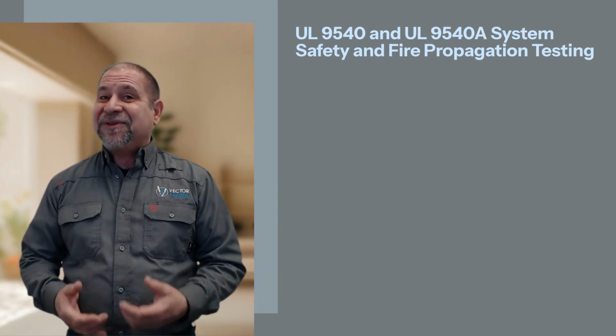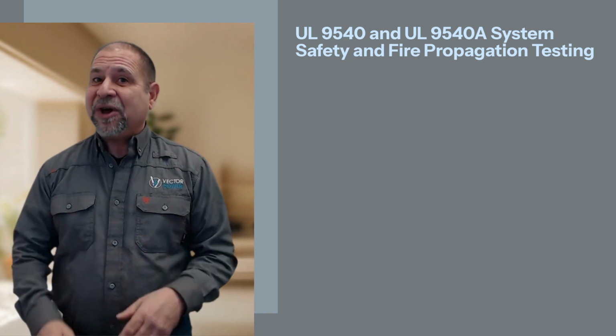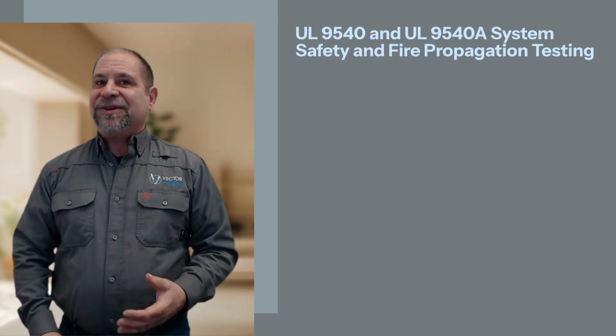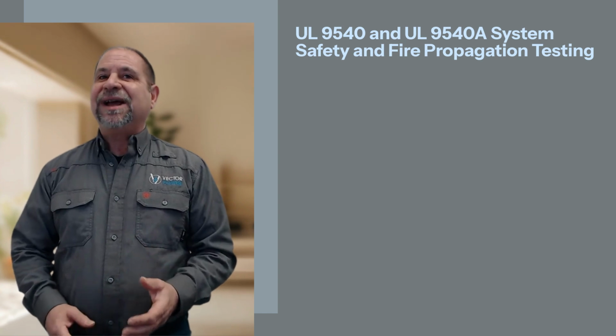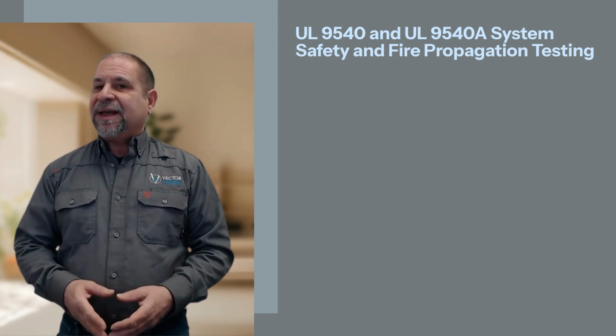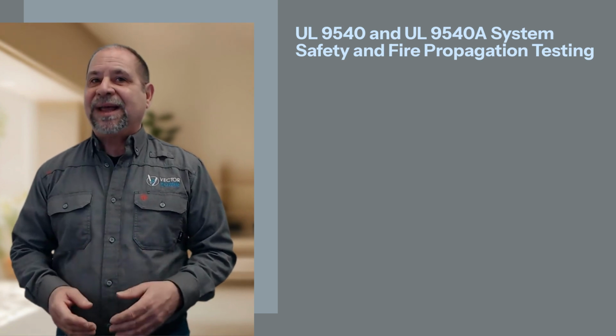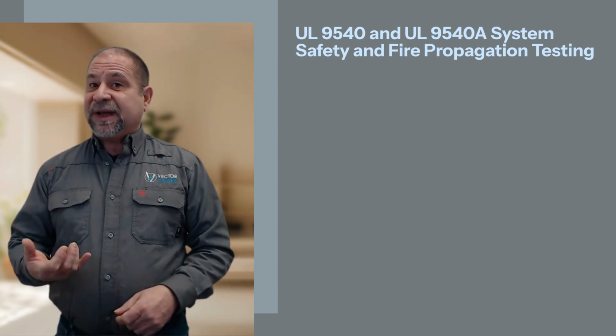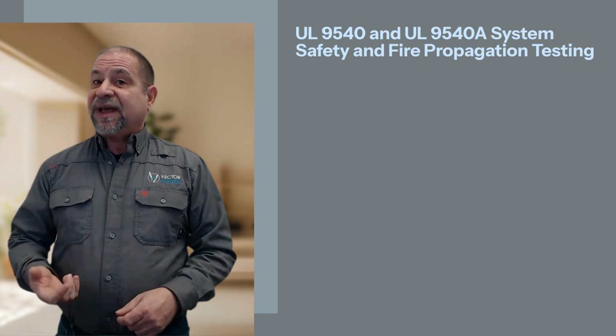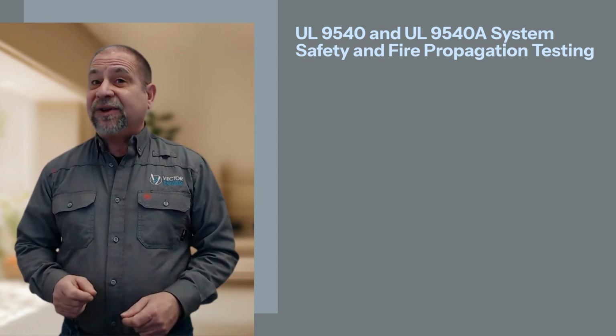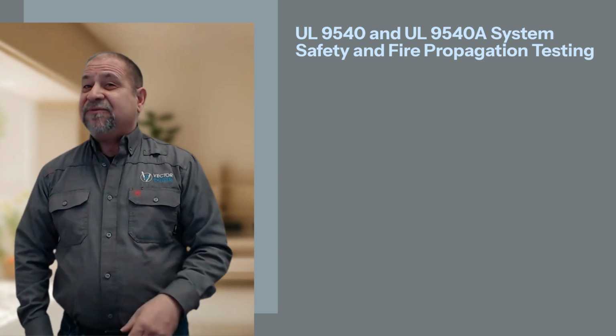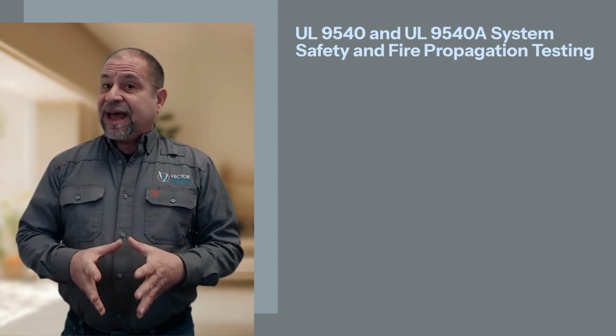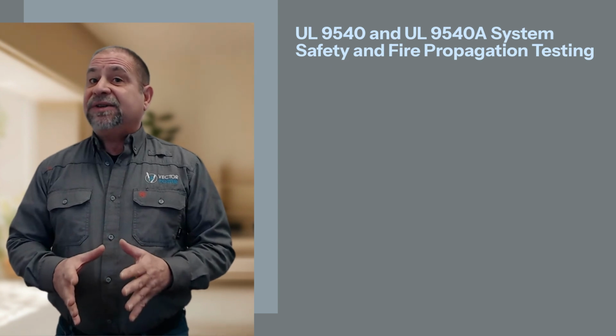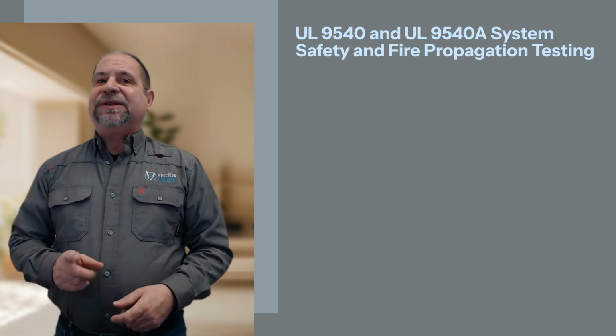NFPA 855 and related fire codes explicitly reference UL 9540 and UL 9540A. In many jurisdictions, energy storage systems over certain energy thresholds must be certified to UL 9540 and tested to UL 9540A to be accepted by the authority having jurisdiction.